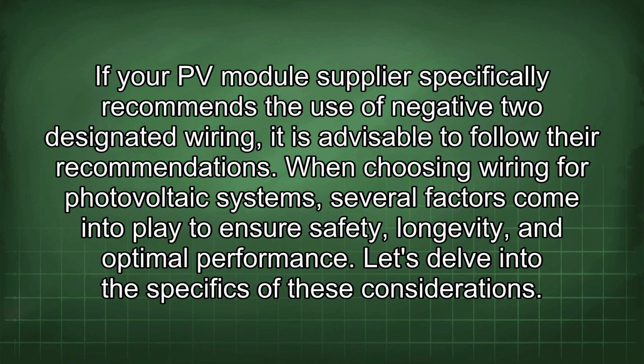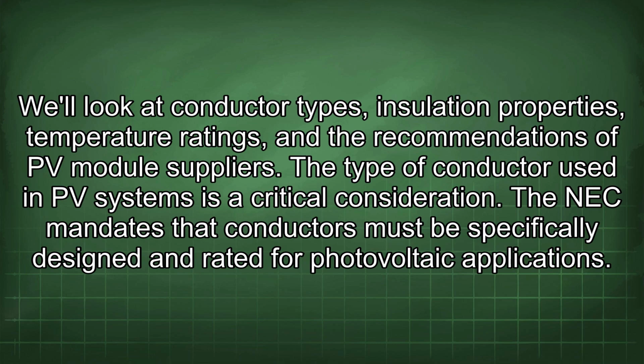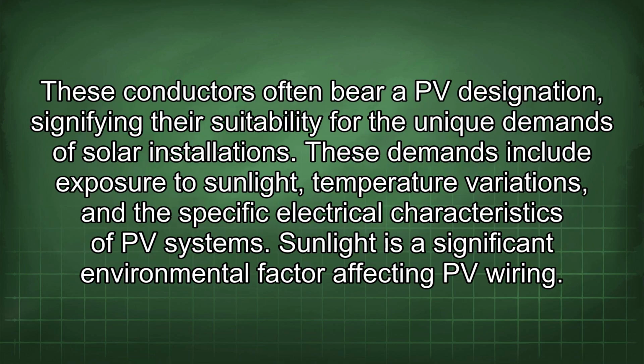When choosing wiring for photovoltaic systems, several factors come into play to ensure safety, longevity, and optimal performance. Let's delve into the specifics of these considerations. We'll look at conductor types, insulation properties, temperature ratings, and the recommendations of PV module suppliers. The type of conductor used in PV systems is a critical consideration. The NEC mandates that conductors must be specifically designed and rated for photovoltaic applications. These conductors often bear a PV designation, signifying their suitability for the unique demands of solar installations. These demands include exposure to sunlight, temperature variations, and the specific electrical characteristics of PV systems.